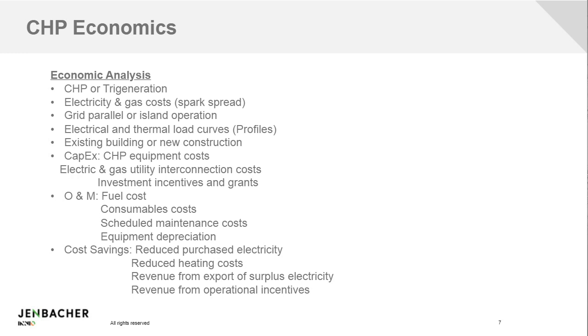Looking at the sizing of the project, we have to look at the electrical and thermal load curves - the load profile. Throughout the day and year you'll have varying electrical and thermal loads, and you try to match that to the output of the generators to determine the size and number needed. For that reason it might make sense to have more than one - running one generator in base load and turning on a second during peak hours.